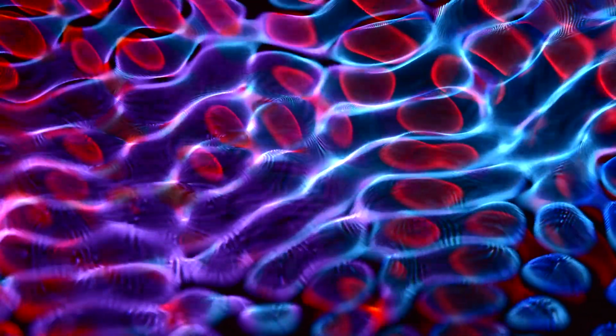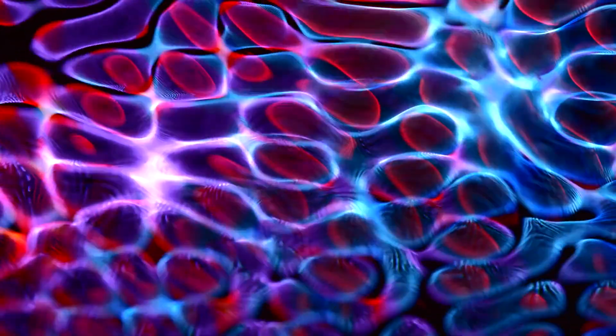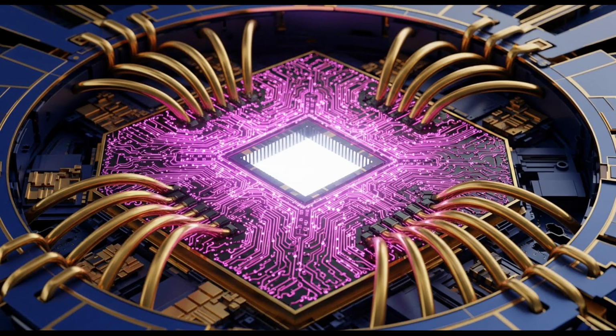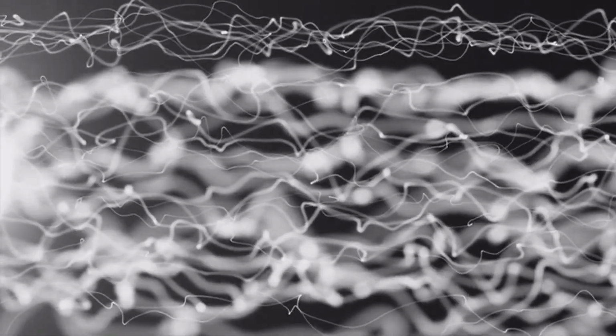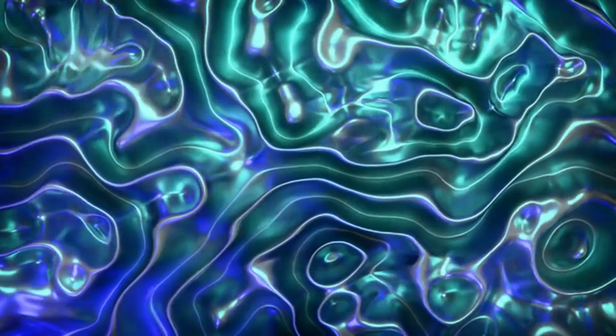Here's how Rubin fundamentally changes the game. Instead of liquid cooling that tries to keep everything cold, Rubin uses direct-to-chip liquid cooling at much higher temperatures. The key innovation is accepting 45 degree Celsius water, about 113 Fahrenheit, directly onto the GPU die. Normal PC water cooling maxes out around 30 degrees Celsius to stay safe. Rubin just doesn't care about staying cold, the chips are engineered to tolerate the heat.